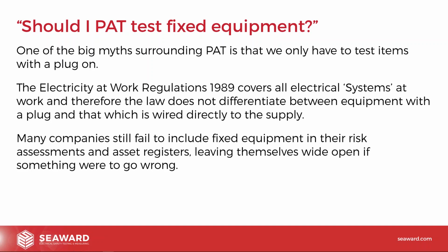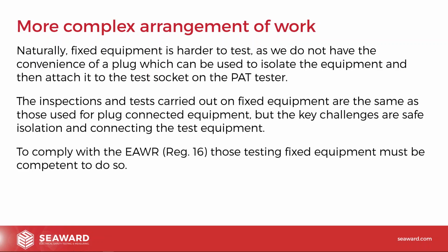So it is important that we make sure that we're actually covering those items as well when we do our risk assessments to determine who is actually going to test these, because the problem is we get assumption going on. We either assume the electrician does it when they do the EICR, or we assume the PAT tester's doing it, and in reality, a lot of the time, neither are doing it, and that's the problem that we've got. Now, testing fixed equipment is harder because we don't normally have the convenience of a plug, which can be used to isolate the equipment and also to attach it to the socket on a PAT tester. Generally, the inspection tests we carry out on fixed equipment are pretty much the same as we would do on plug connected equipment, but the key challenges are how do we safely isolate it and how do we actually connect it to the tester.